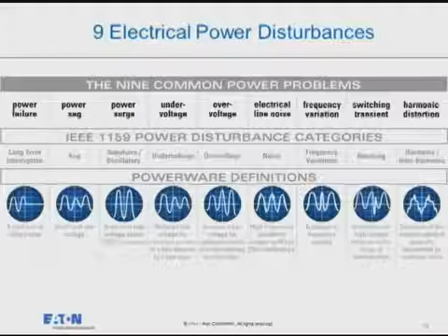Then we get into the last four. Line noise, frequency variations, transients, harmonic distortion, steady state types of problems that exist in an electrical network or an electrical infrastructure, typically induced by the loads themselves in the environment itself. This isn't a utility problem typically. This is in the buildings that we have. And they're steady state. They're just a function of the nature of the application or the environment we operate in. It's not an event. It's part of an electrical problem.